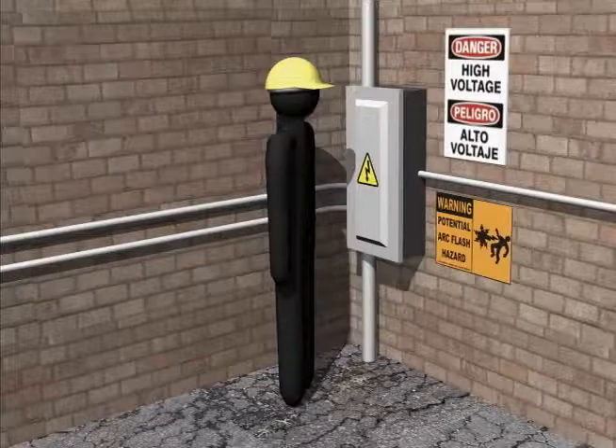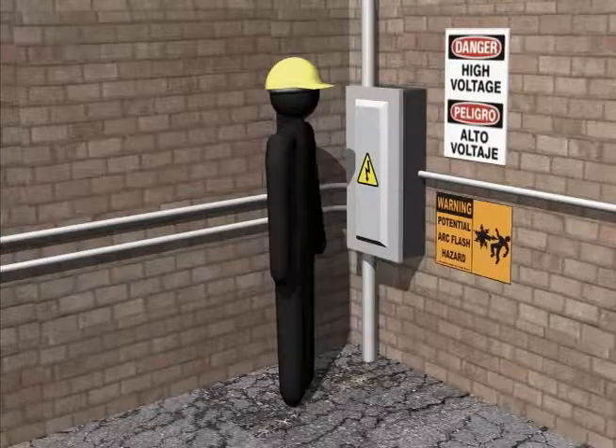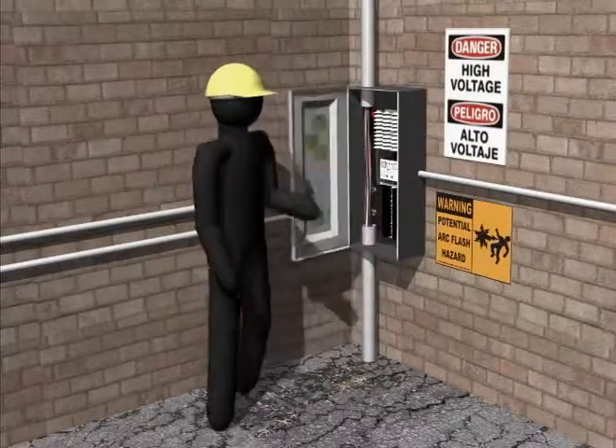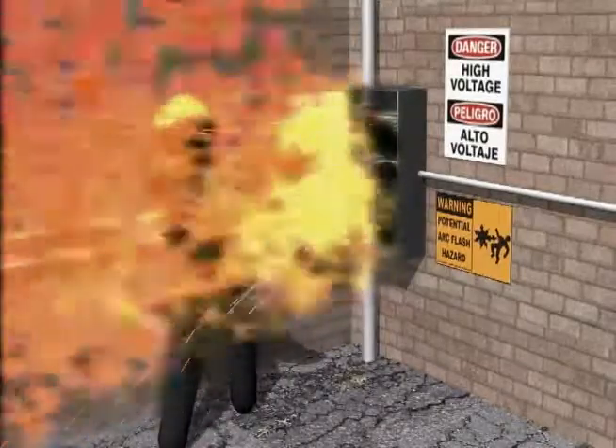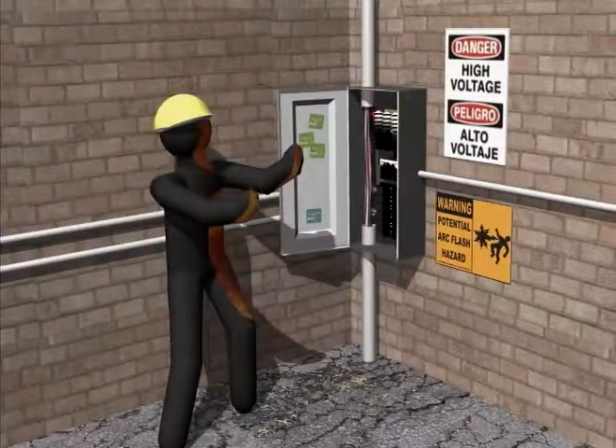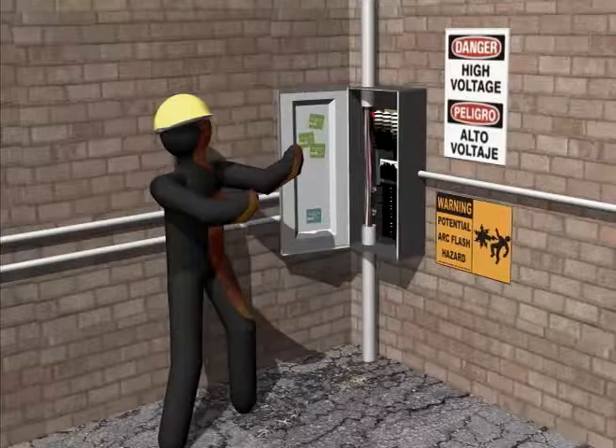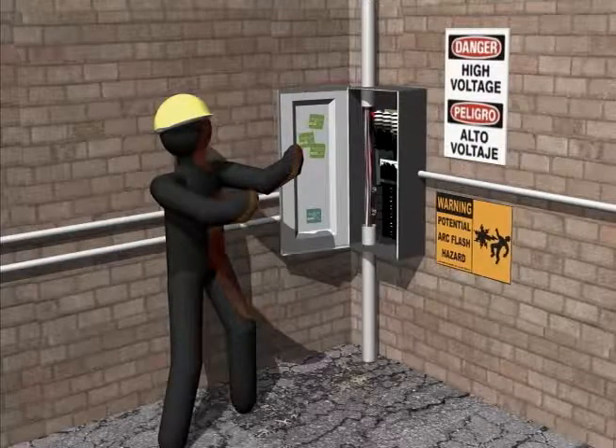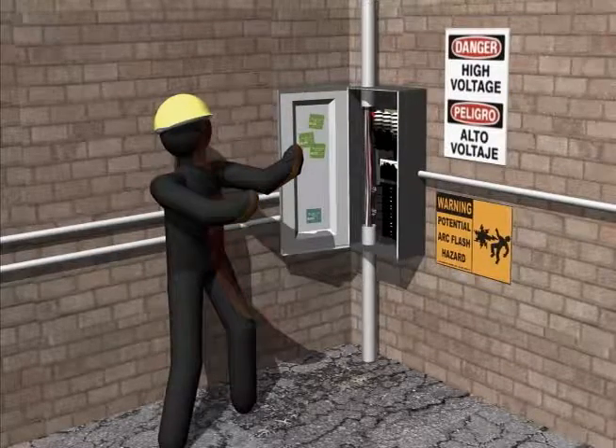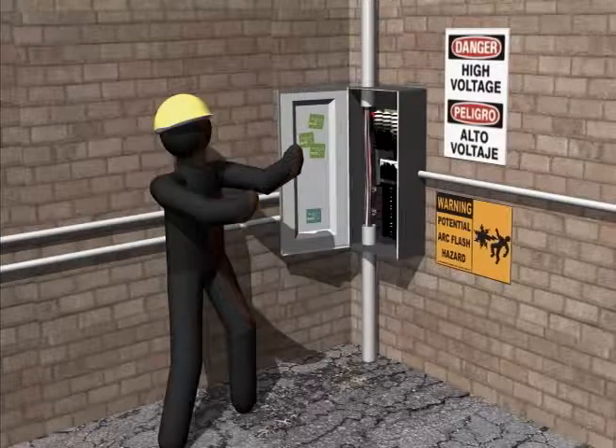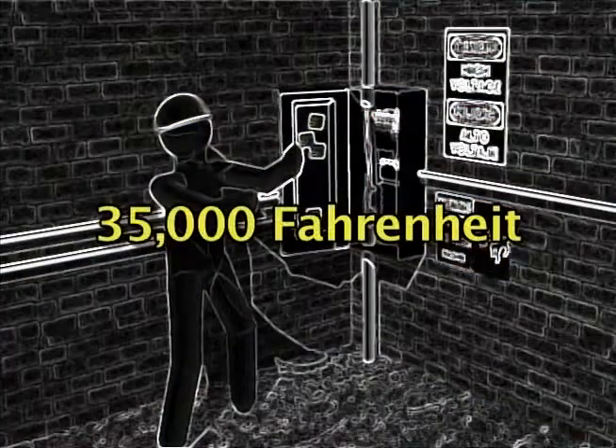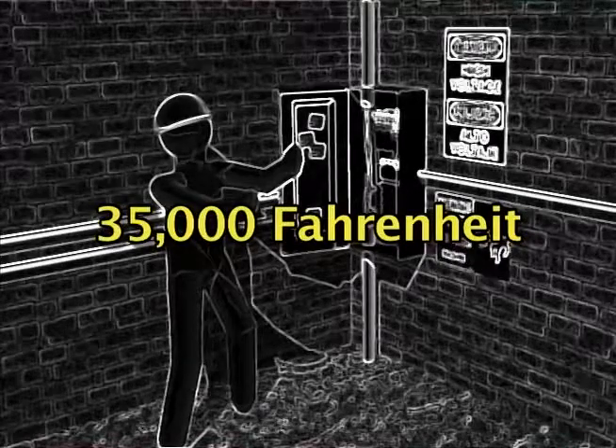Arc flash is one of the most intense forms of electrical hazards. It is the sudden release of electrical energy through the air when a high voltage gap exists and there is a breakdown between conductors. An arc flash gives off thermal radiation, heat, and bright, intense light, both of which can cause burns. Temperatures as high as 35,000 degrees Fahrenheit have been recorded from some arc flashes. High voltage arcs can also produce significant pressure waves by rapidly heating the air and creating a blast.